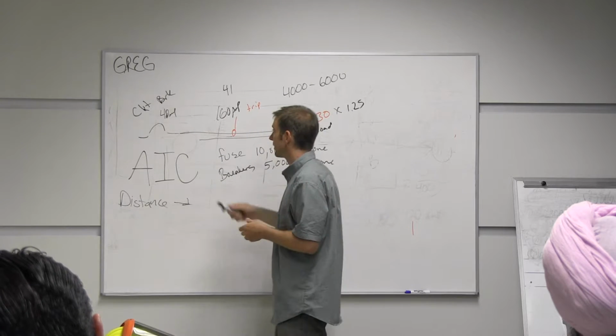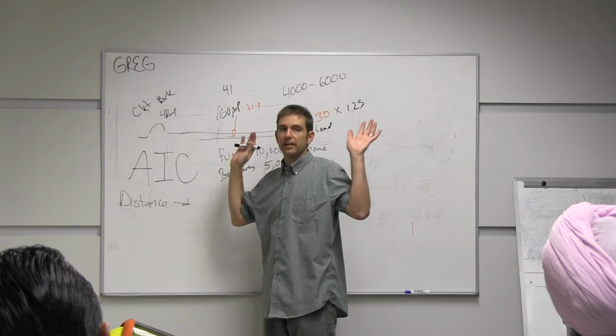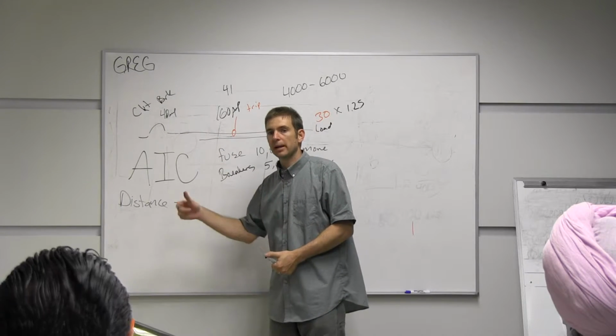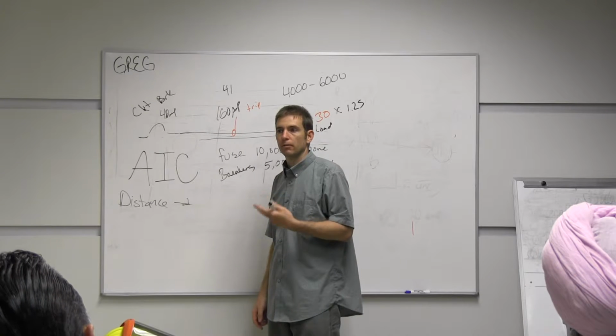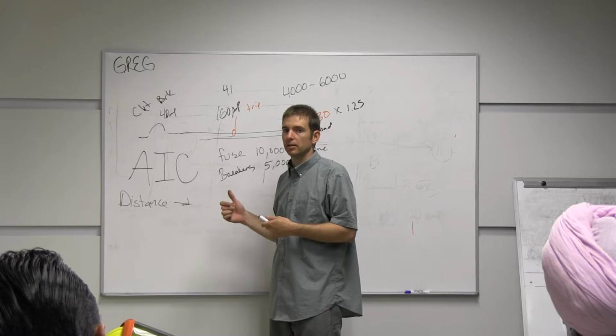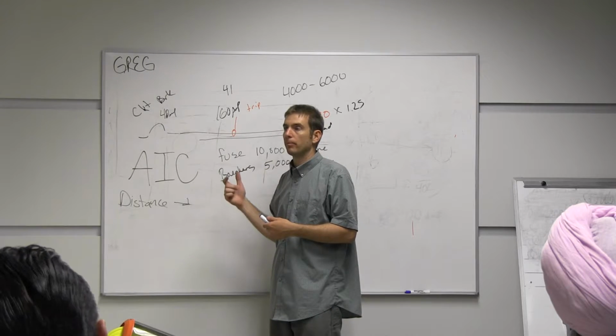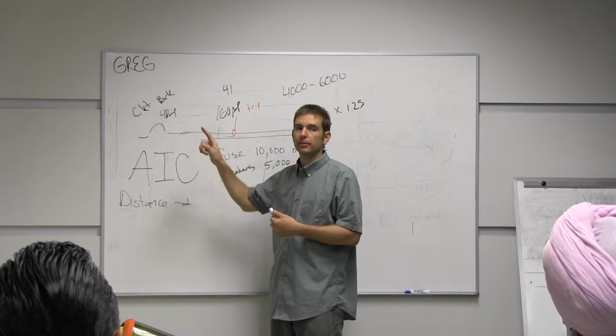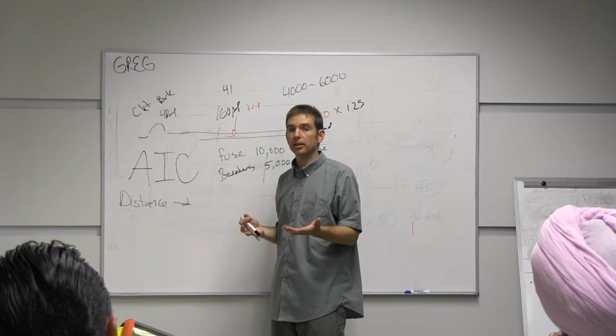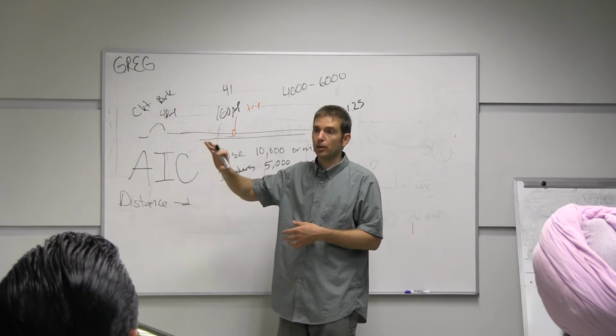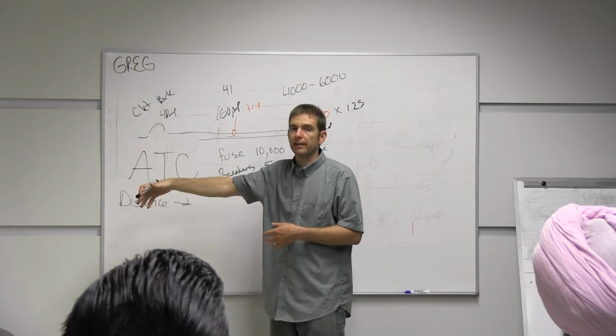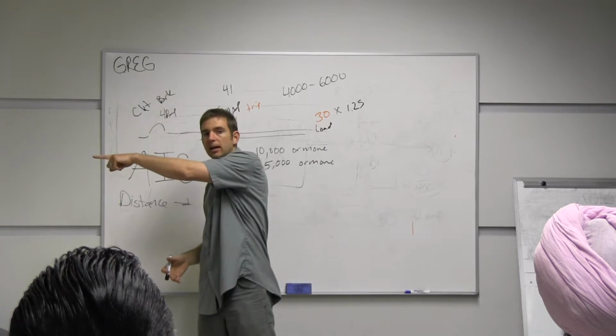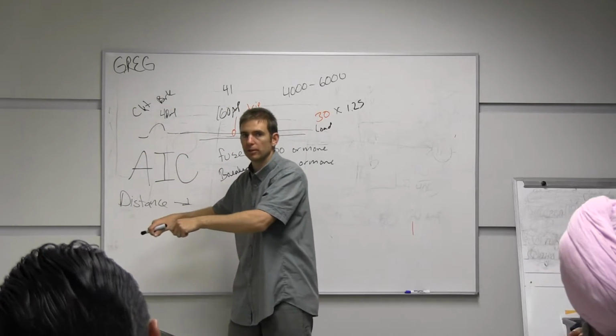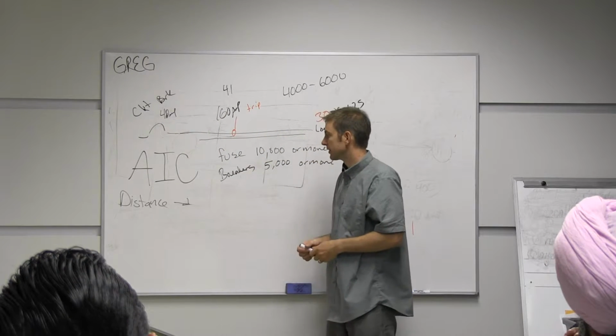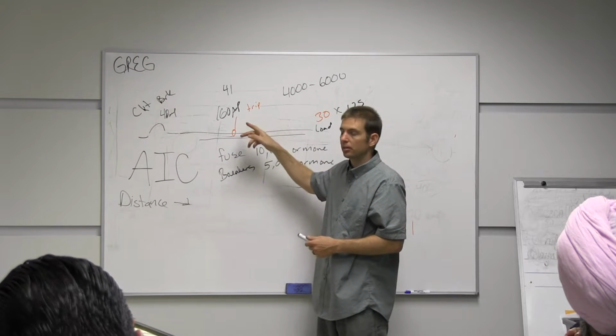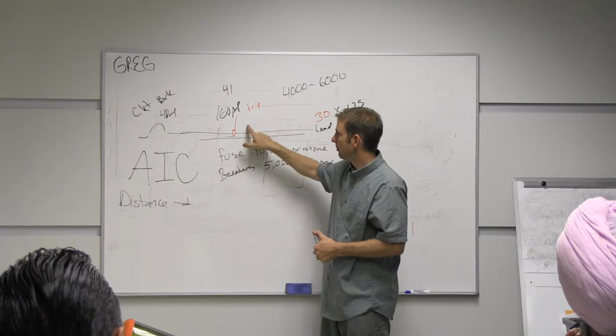So if I'm at a circuit breaker and I have a 40 amp circuit breaker and my breaker's tripped and someone said, hey, the lighting's off, and I go over there and I see the circuit breaker's tripped and I turn it back on, 1, 2, 3, 4, 5. 5 seconds, the circuit breaker trips again. That's telling me that I have a fault of some sort, but my problem is probably farther away than being close to the panel, which is kind of good for troubleshooting. We know that, well, it's likely, not always true, but likely I have a problem far away, and now I can start, if I'm going to be splitting a circuit, I'm going to split the circuit down a ways as opposed to, right, I'm not going to start troubleshooting right next to the panel. It has other benefits too, but again, because it's farther away, it's going to reduce the amount of fault current.